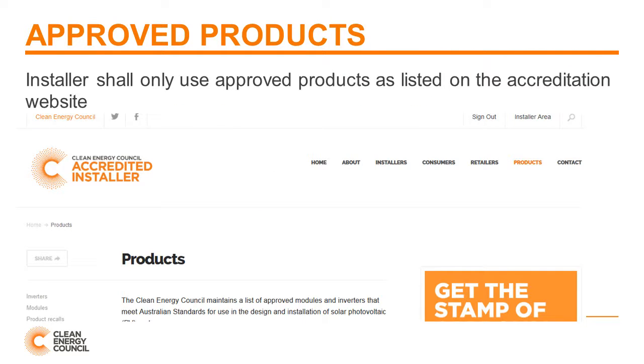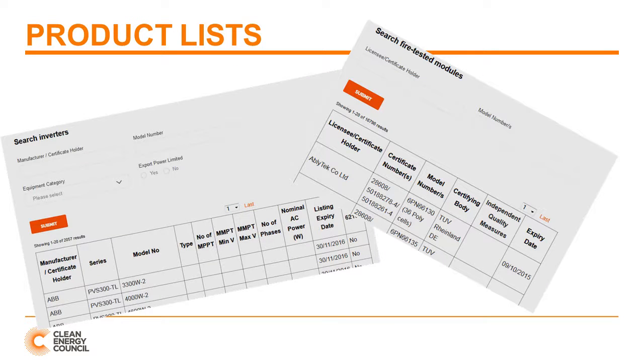Be aware that if you wish to claim Small Scale Technology Certificates, or STCs, you must only install CEC-approved PV modules and inverters. To find such lists, refer to the Product section on the screen. Note that you do not have to log into the Installer area to access this section. By only installing products on the approved lists, you can be confident that your components meet the relevant requirements as set out in the applicable standards. This is a basic requirement for creating STCs, and also a requirement of State Electrical Safety Acts. For example, when installing modules on a building, you must ensure they meet Fire Class C. If you install a module from the PV module list on the screen, you have the confidence of knowing that you are complying with the requirements set out by the Clean Energy Council, Clean Energy Regulator, and the Electrical Safety Regulator.